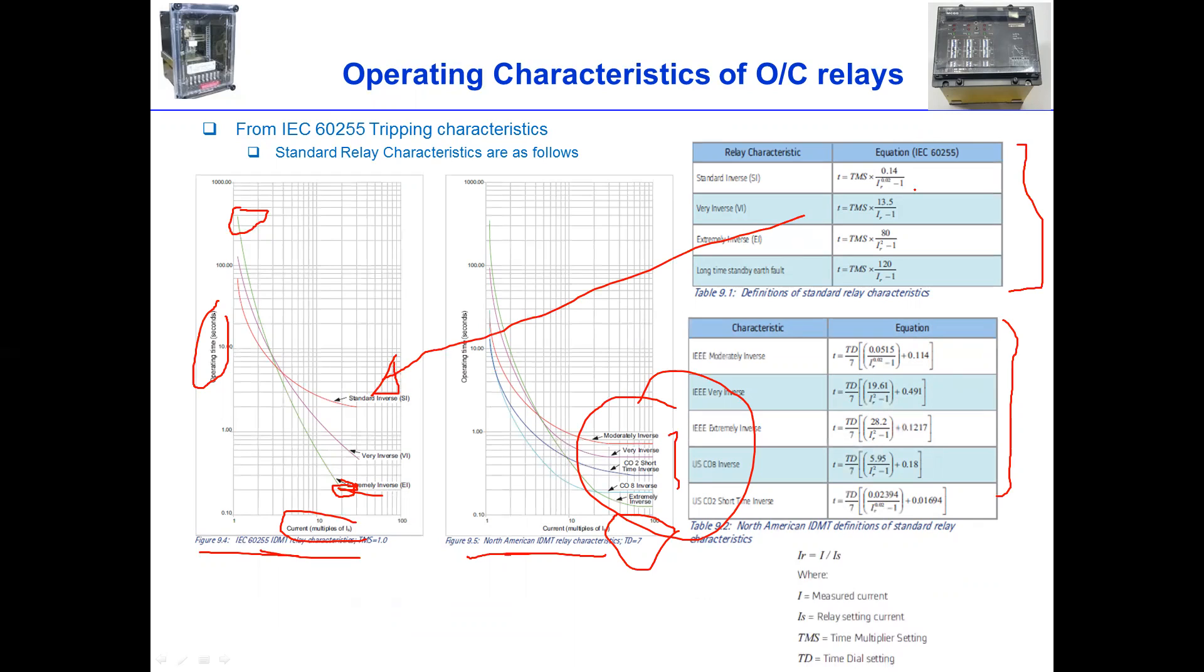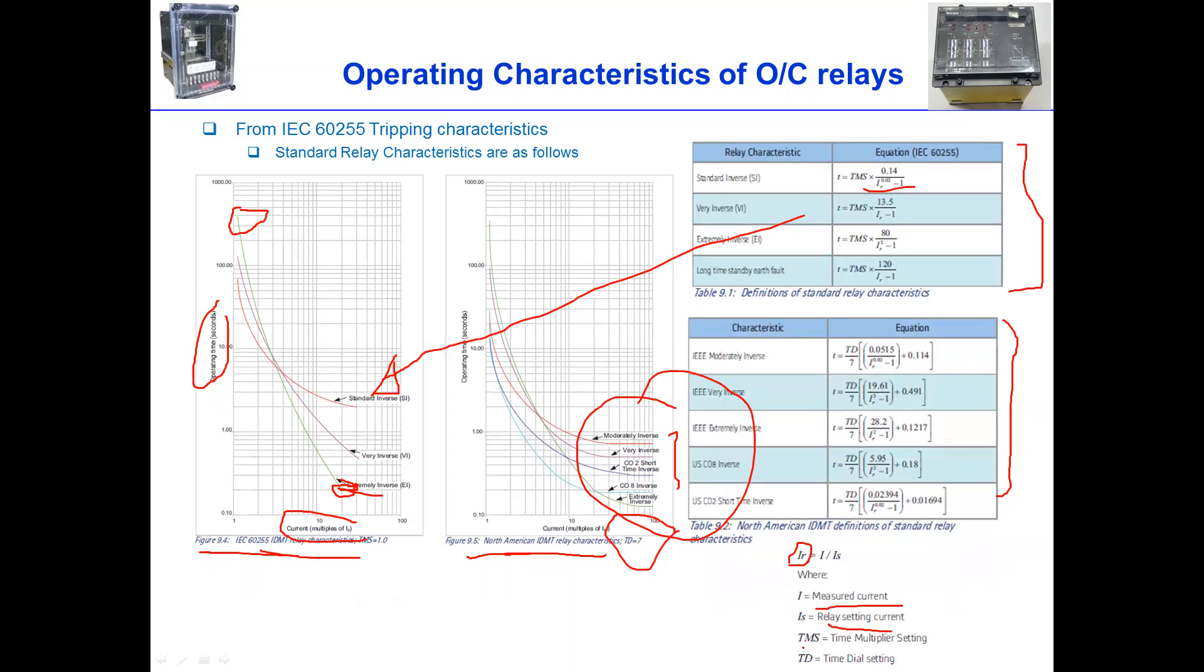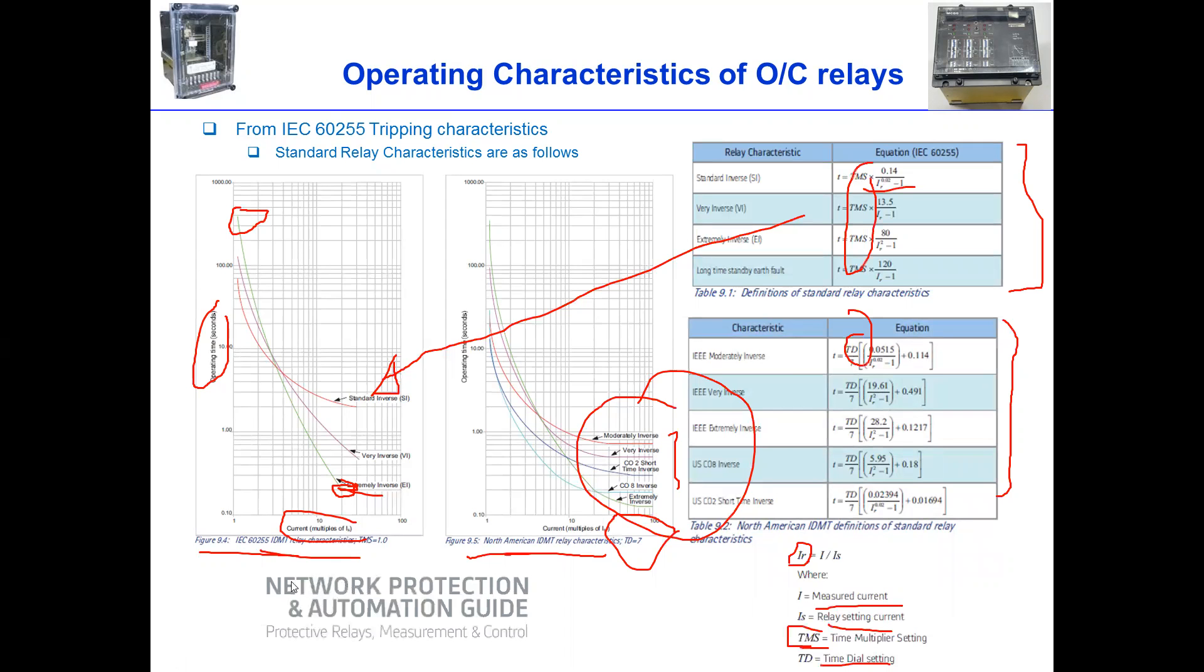And the meanings on here are, for example, IR means current divided by setting current. That means the pickup or setting current IR is the ratio of the current or the input current divided by the setting current. And of course, I measured current given the fault. And this is the relay setting current. And of course, TMS is time multiplier setting. And TD is time dial, which TD is used more in American standard. And TMS is more used in the European standard. We can see this clearly in Network Protection and Automation Guide book, which is Alstom's Protection Relays book.